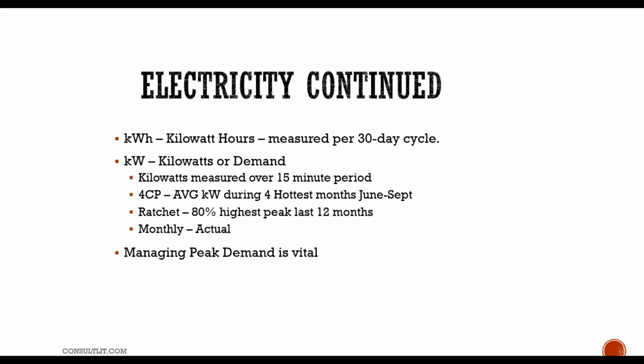annual peak demand. So if I say I average 200 kilowatts every 15-minute period, then one day I turn everything on during a hot day, all the lights, all the HVAC, and I go from 200 to 350, even for one 15-minute period. They're charging you the 350, not the 200 or even the average. They're charging you the 350. So how and when you use your electric equipment makes a huge impact.